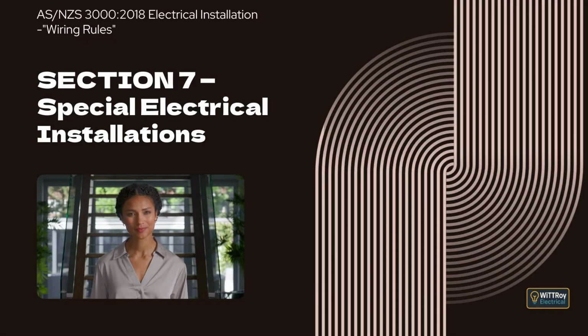Clause 7.4.8.2, Single items of electrical equipment. This clause explains that where a single item of equipment is supplied from a separated circuit, separation must be verified by testing in accordance with the general testing clause and by measuring insulation resistance between earth and the exposed conductive parts, or the earth contact of a socket outlet.